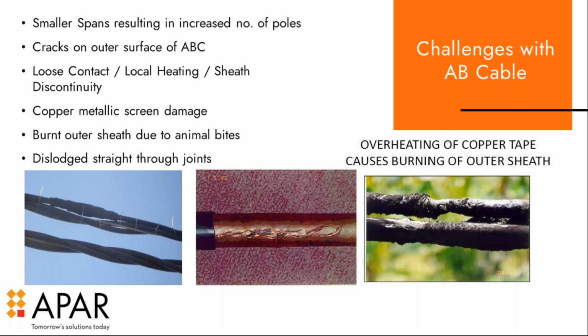Burnt outer sheath due to animal bites, because the outer sheath is PVC or HDPE - this is all vulnerable to animal bites too. Squirrels have very sharp teeth and create problems. Then there's dislodging of the straight-through joint, because we use joints there, and if workmanship is not good, dislodging of the joint also appears.